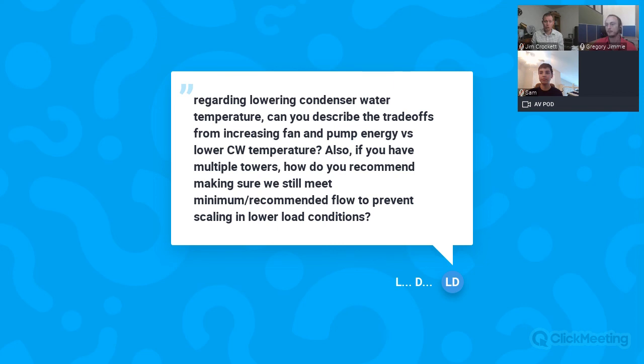So that would basically mean that instead of running one tower at full flow or design flow, you could run two at 50% flow. So that would be without changing your pump speed. One thing to note is that chillers also have a minimum. So you need to be above basically the greater of the two. So if your tower has a lower minimum flow than your chiller does, your chiller gets to rule the roost in that case. So make sure your chiller is taken care of.